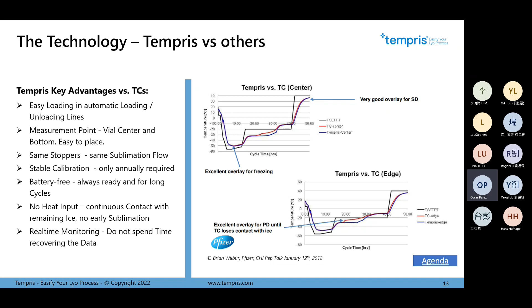And then, of course, real-time monitoring, as I mentioned—you have the values instantly, in real time. You don't have to wait until the cycle is done and take the sensors, put them in a special loader or table, get the data, and then export it to other formats. We have the data at the same time it's generated. So we close the door of the freeze dryer and we know exactly what's going on with the product in these critical positions that we recommend measuring.